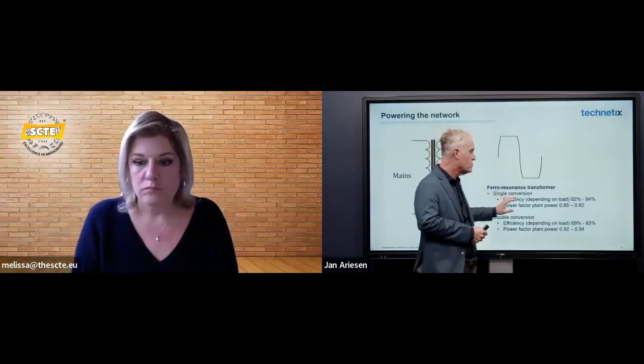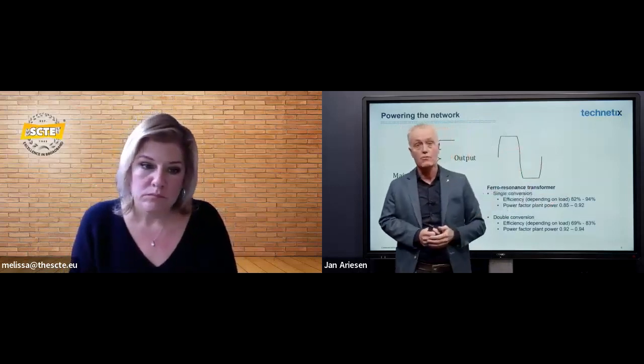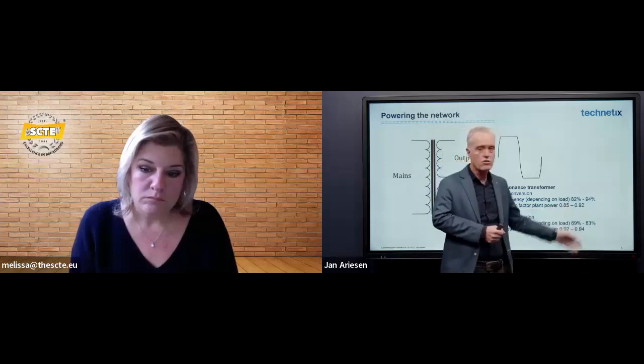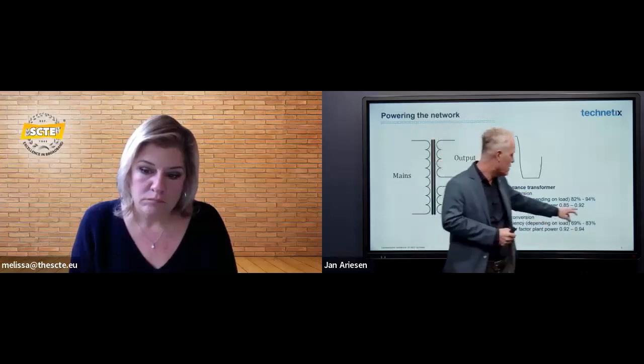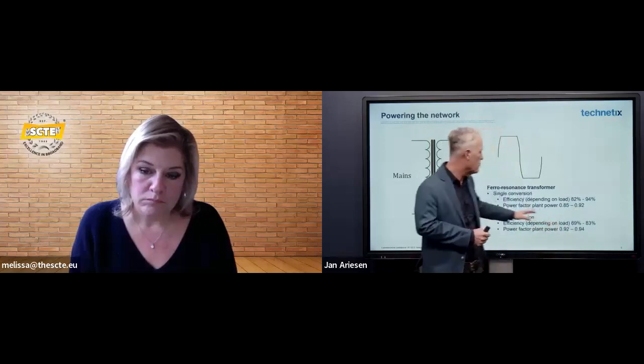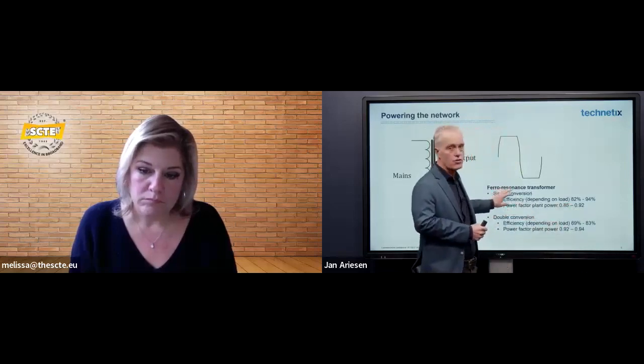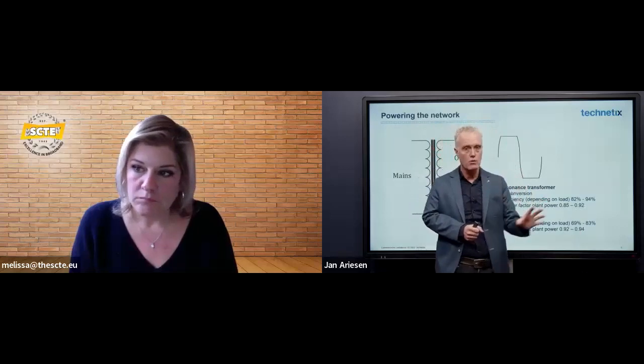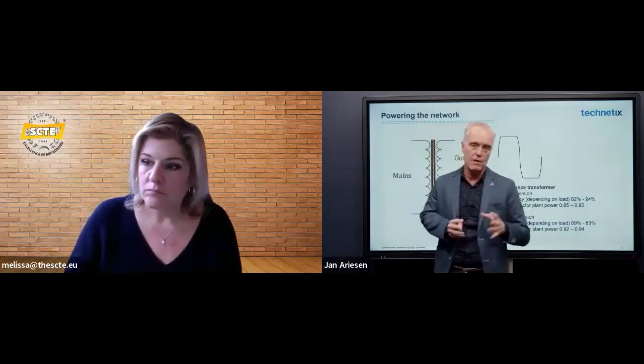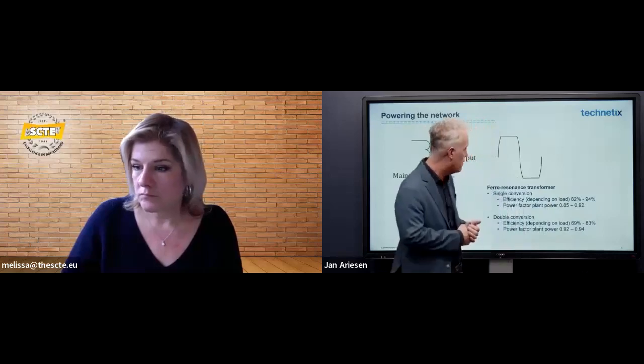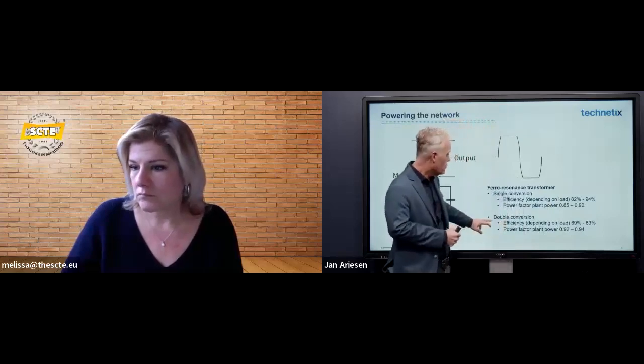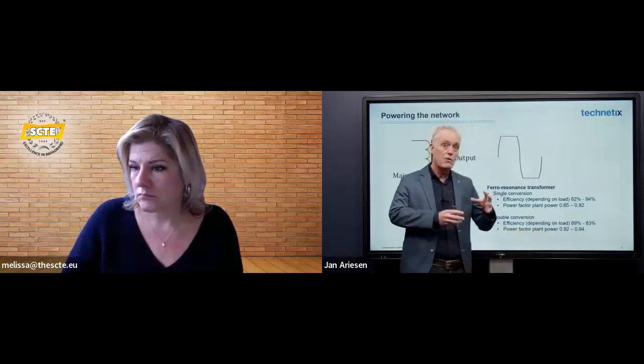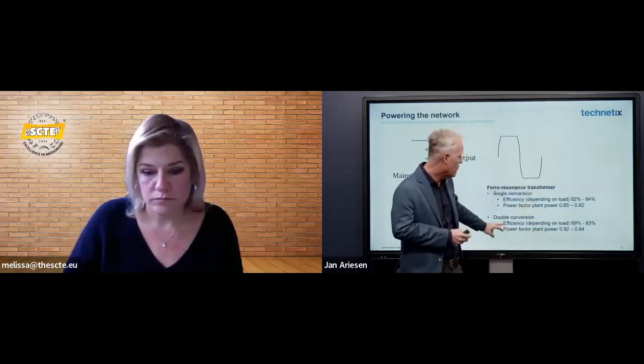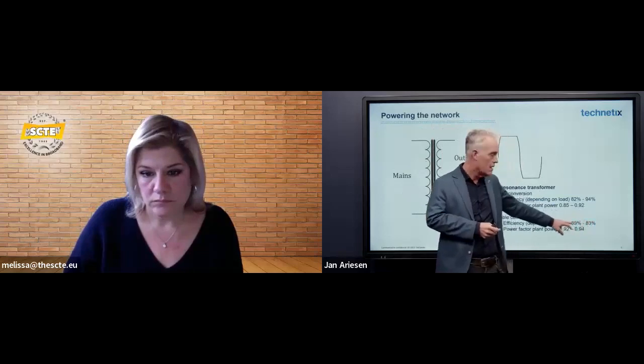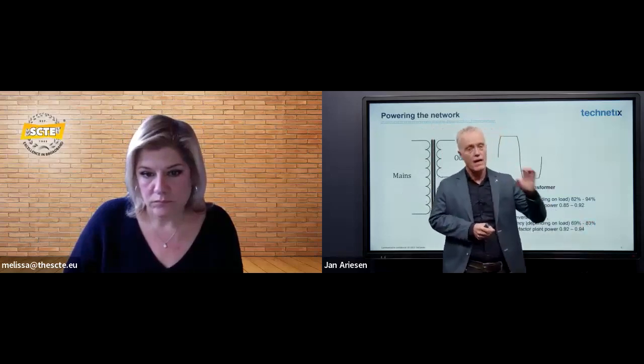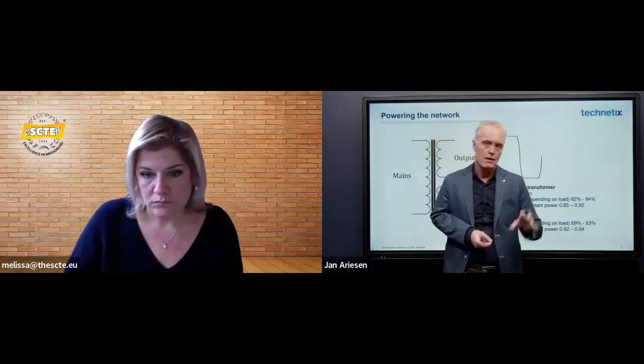The single conversion efficiency is about 82 to 94%. And the power factor is somewhere between 0.85 and 0.9. That is single conversion. Mostly double conversion is used, and that's also because it has a better entrance for the better backup battery powering. So double conversion is mostly used, and that means that you have twice this step, and therefore you can see that the efficiency is lower. That is between 69 and 83%, and that depends a lot on the loading.